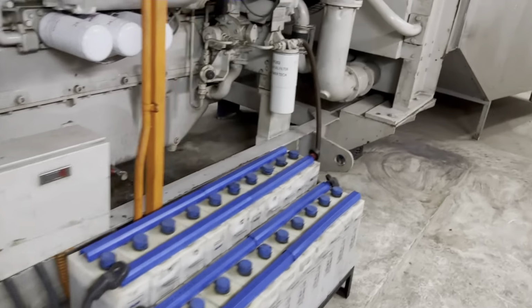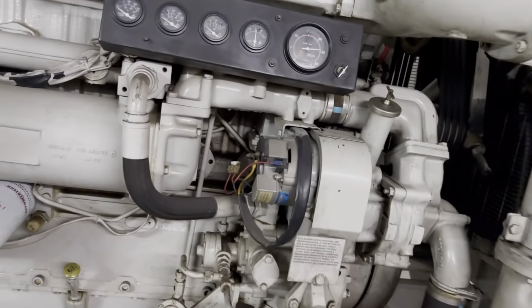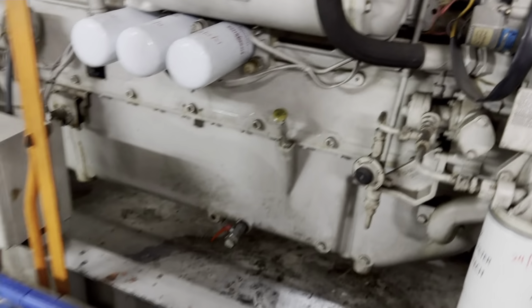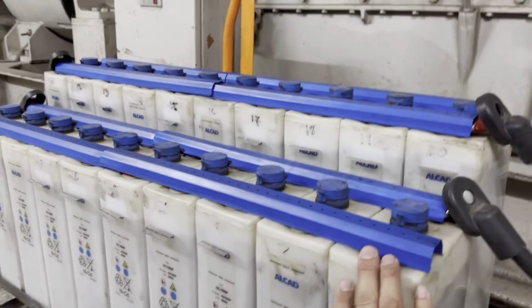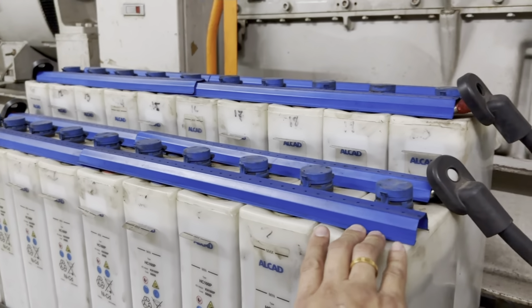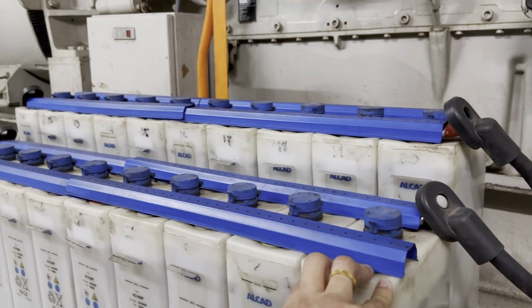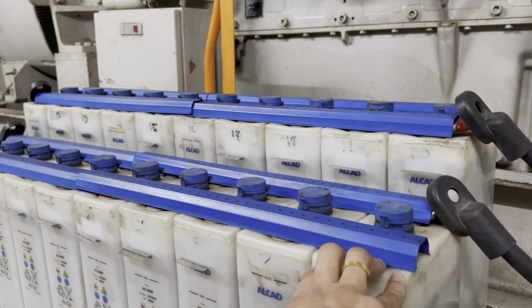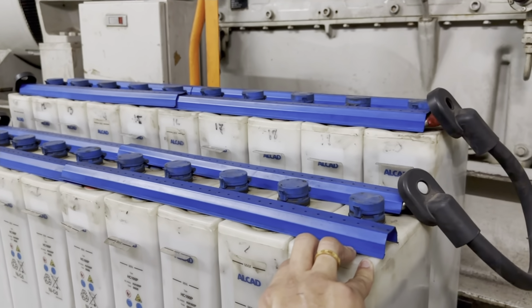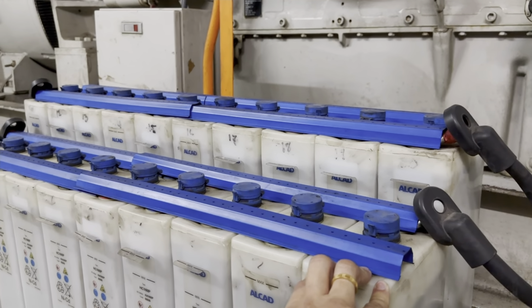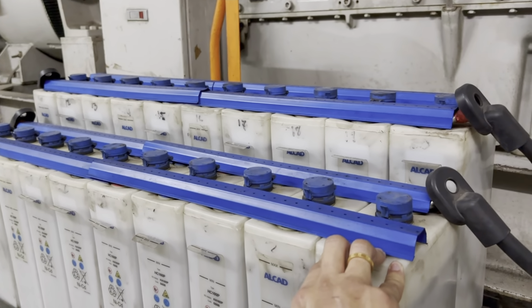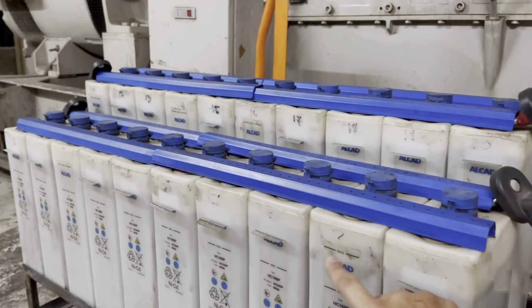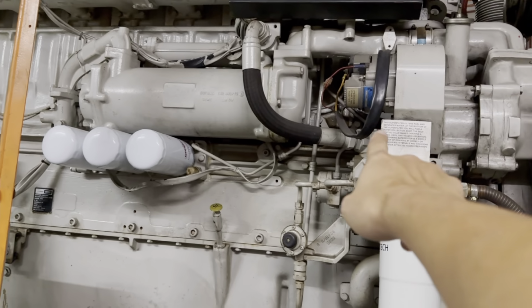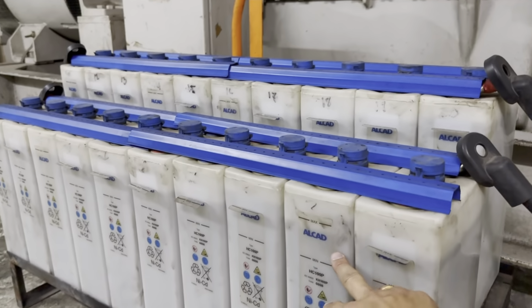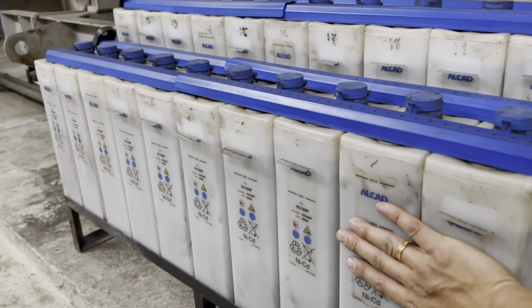If this alternator doesn't charge the battery, it doesn't mean it cannot start — it still can start. But the problem is, if you are operating the genset on load for more than, let's say, a few hours, over time, because the alternator doesn't have any output, it will drain off the voltage at the battery.